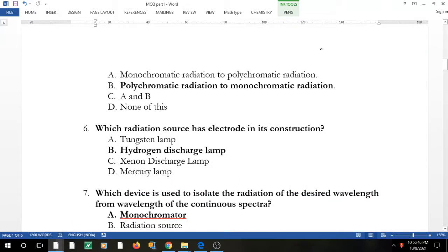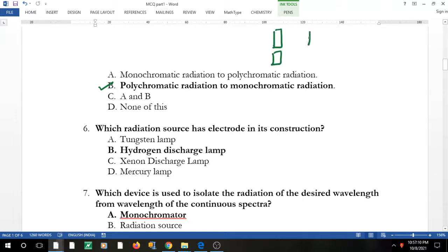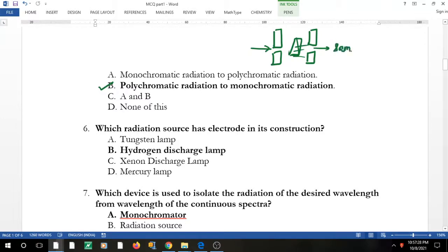The role of the slit is to convert polychromatic radiation to monochromatic radiation. In a UV spectrophotometer, you have an entry slit and an exit slit; in between you have a prism or grating device. The entry slit narrows and converts polychromatic radiation to monochromatic so it falls on the prism, and the exit slit allows only one wavelength to pass, which falls on the sample.